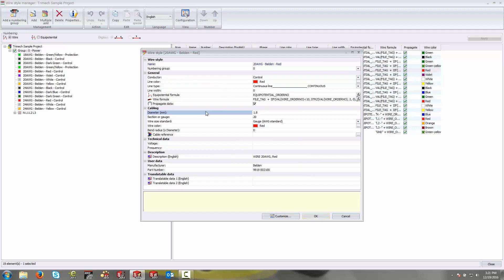Under cabling, you have commands that are related to the physical wire itself. These are a little bit more useful to see on reports. And if you have SolidWorks Electrical 3D, a lot of these properties will be considered. The first is diameter, which specifically refers to the jacket diameter of the wire. This is really only important if you are going to be routing these in 3D using SolidWorks Electrical 3D. This will determine the diameter of the physical wire route.